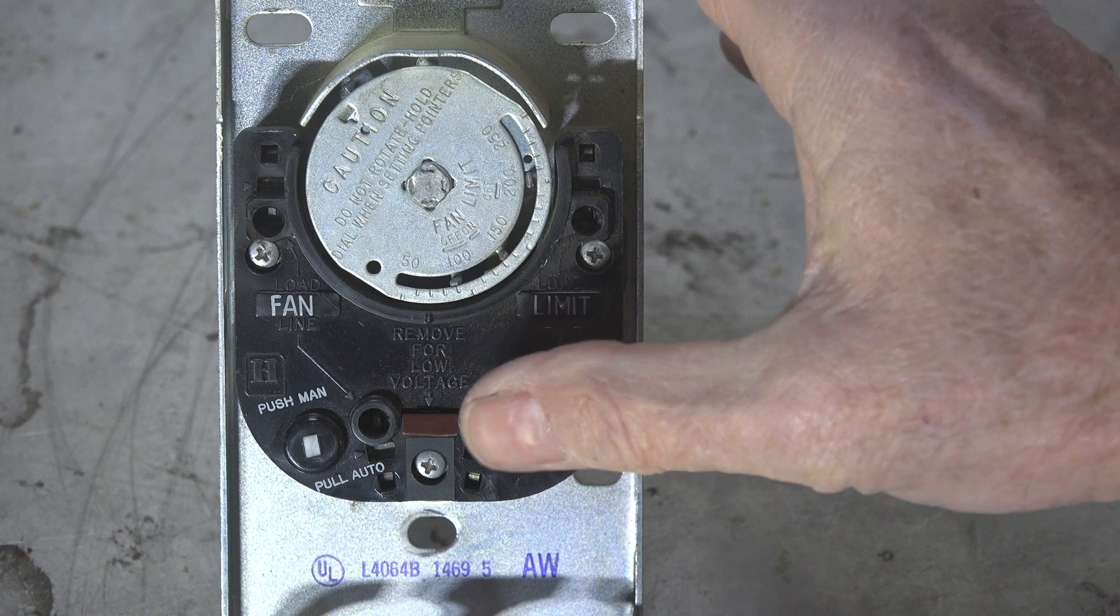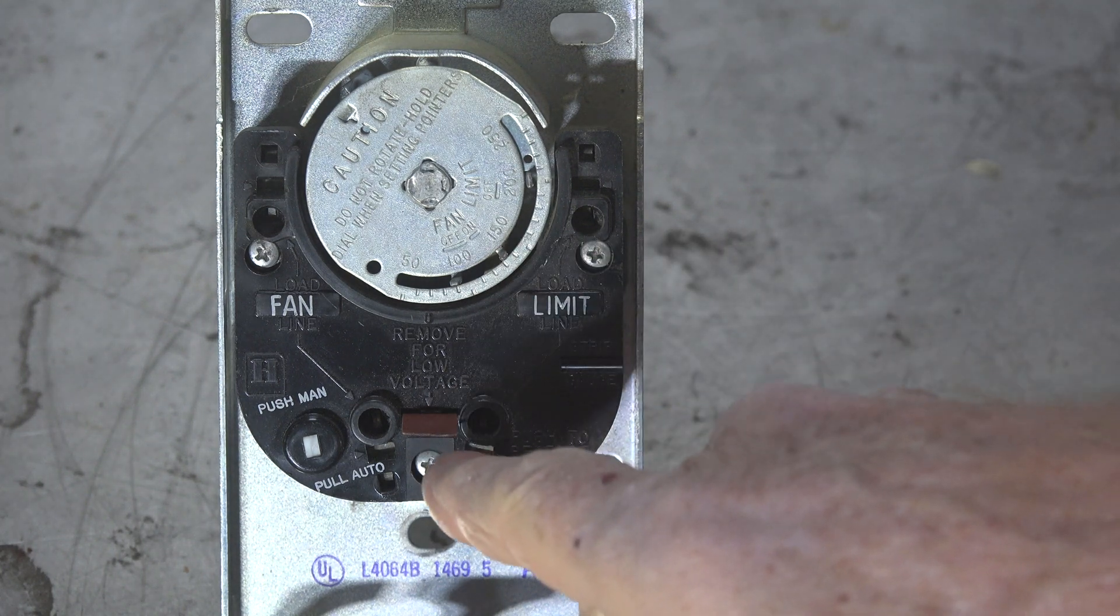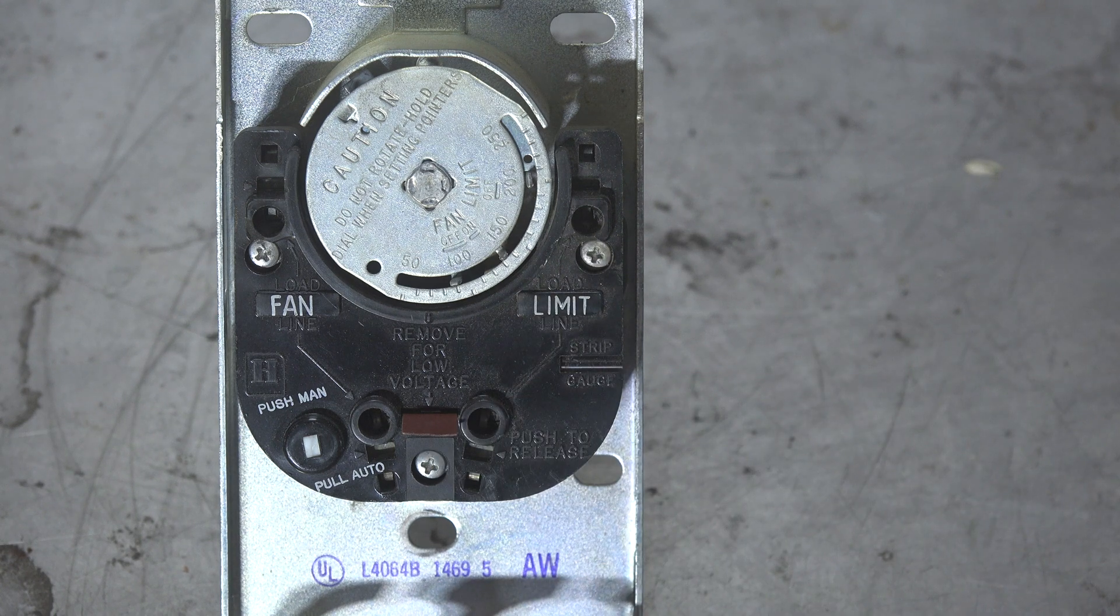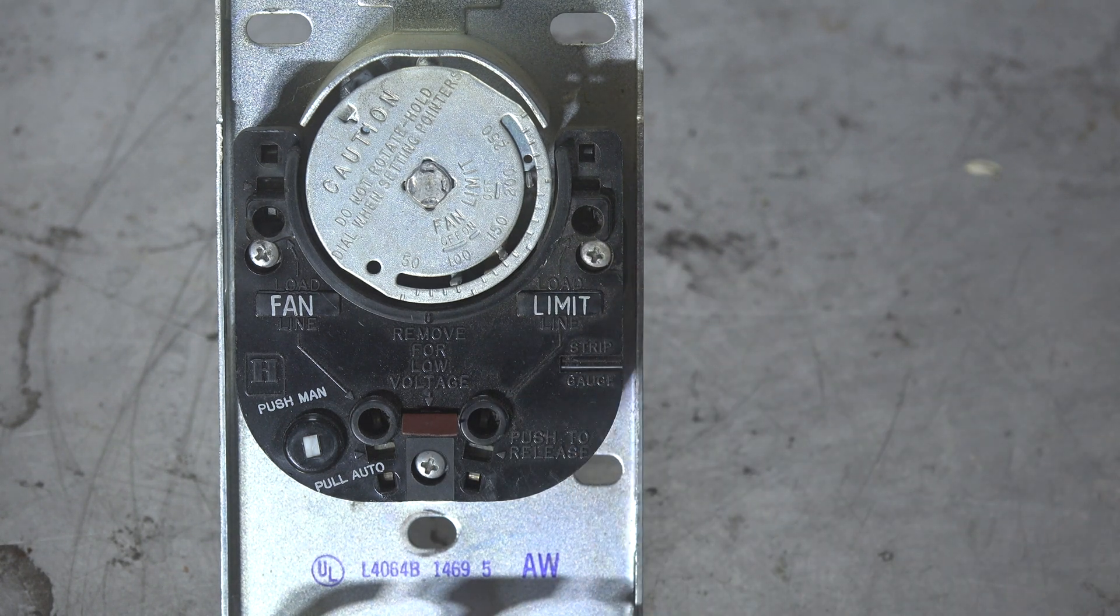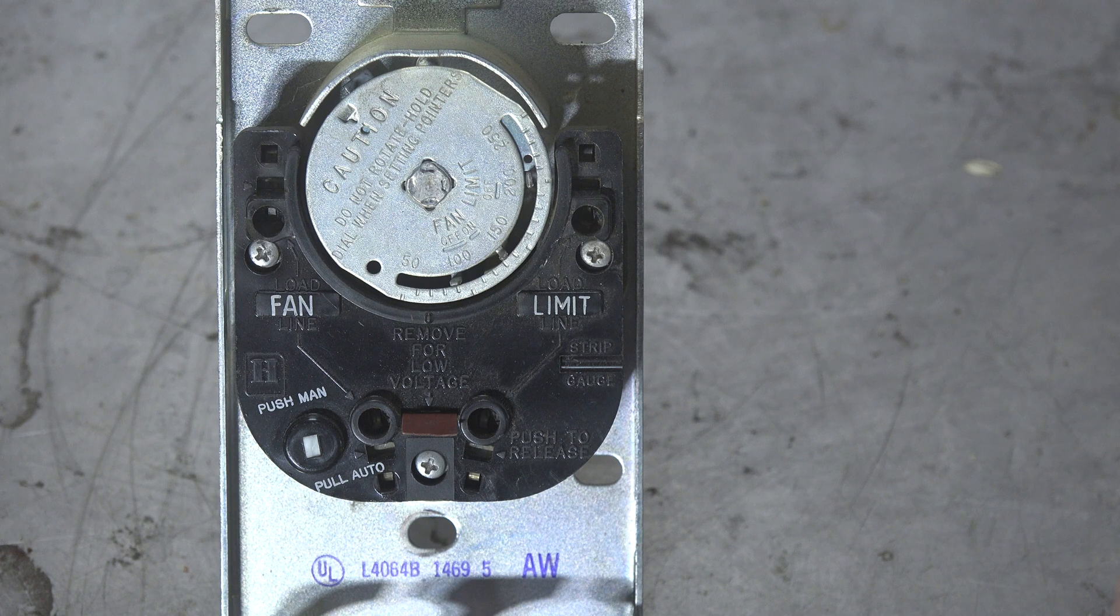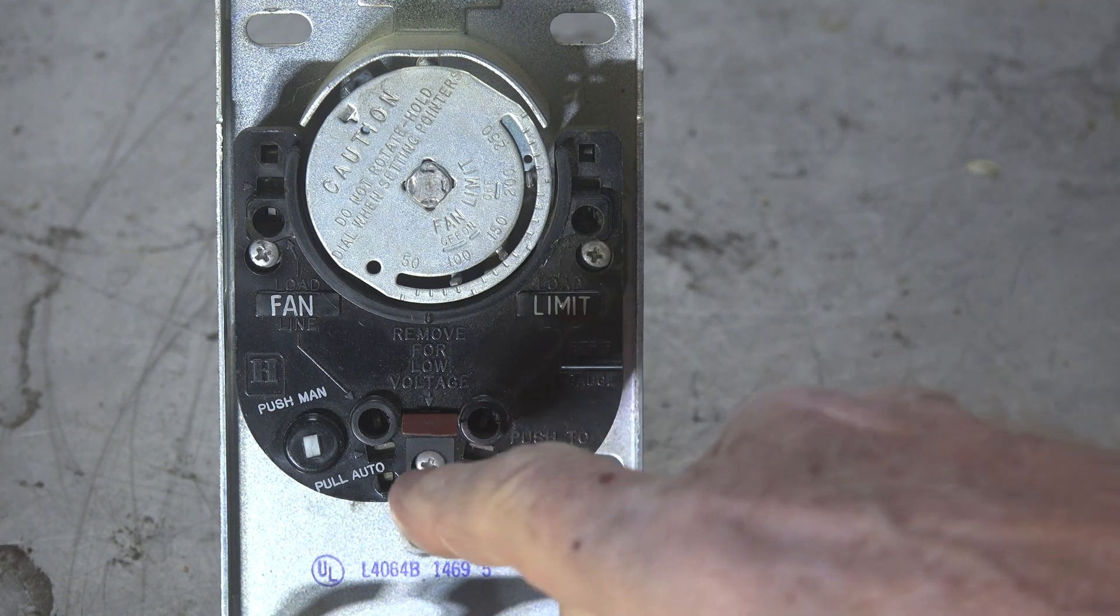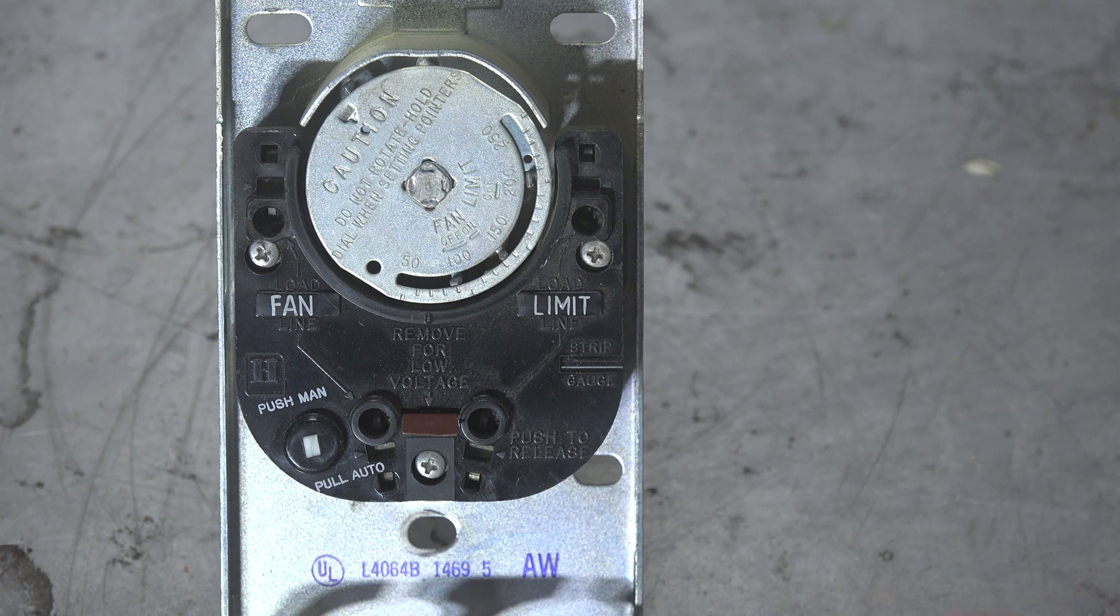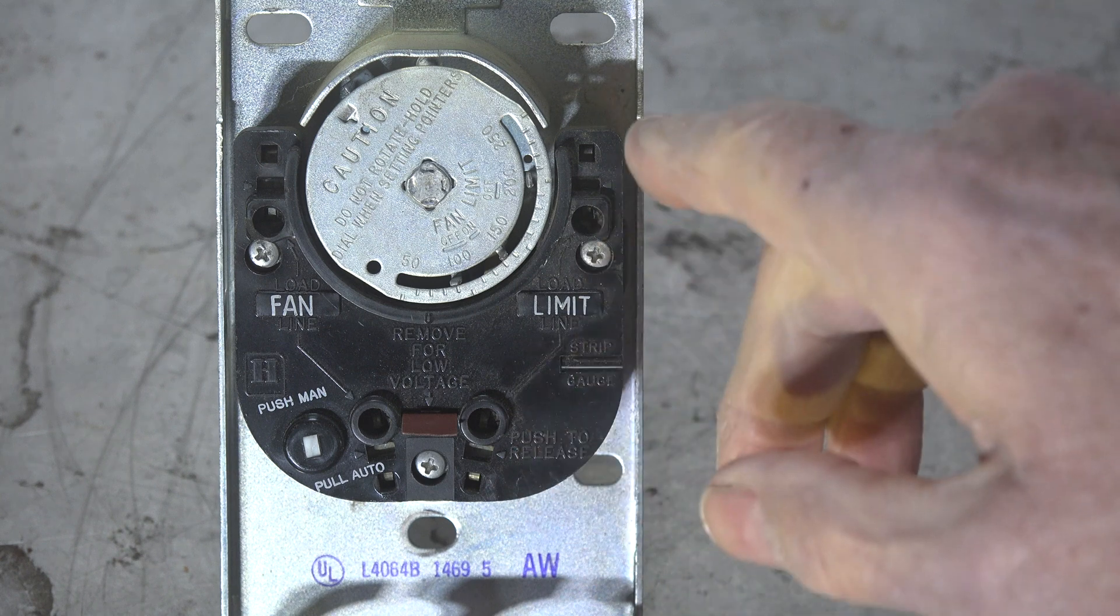This little flappy thing here—it's kind of hard to see—if you pull that out, or there's kind of a copper jumper inside there. Some of them you had to actually take a pair of needle nose and break off that jumper, because you don't want the 120 volts feeding over into the 24. So you break that jumper.